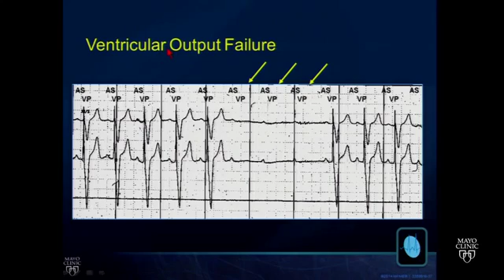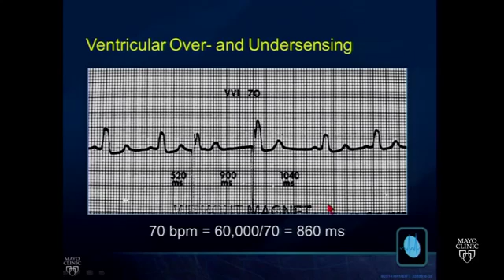Here's an example of both ventricular oversensing and undersensing. The device is programmed VVI at 70, which means that the cycle length for pacing is 860 milliseconds. From this paced beat to this paced beat, it's 900 milliseconds. So something leached into the circuit to cause oversensing and pacing later than should have been the case. The opposite occurs here, where this native depolarization is not sensed by the device such that we pace inappropriately early. That's ventricular undersensing.